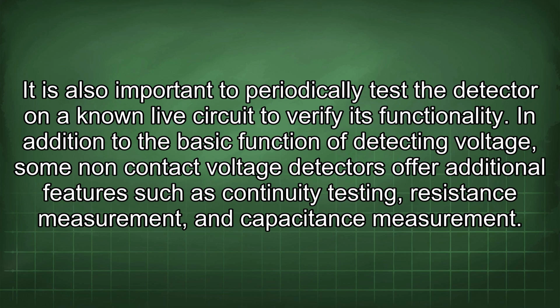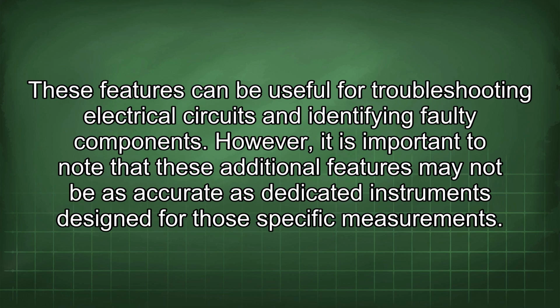In addition to the basic function of detecting voltage, some non-contact voltage detectors offer additional features such as continuity testing, resistance measurement, and capacitance measurement. These features can be useful for troubleshooting electrical circuits and identifying faulty components.